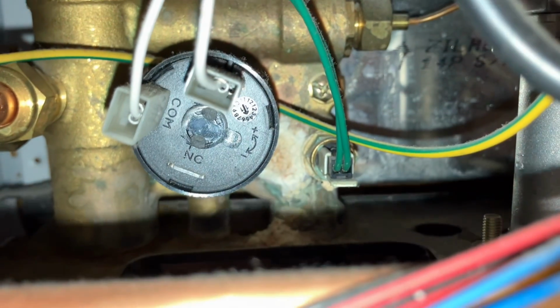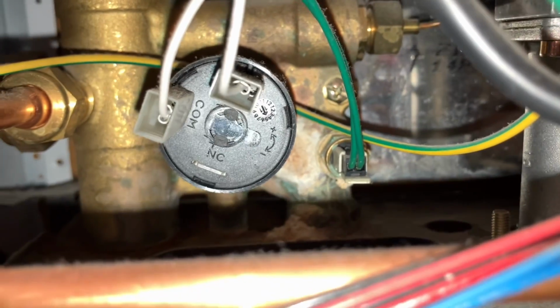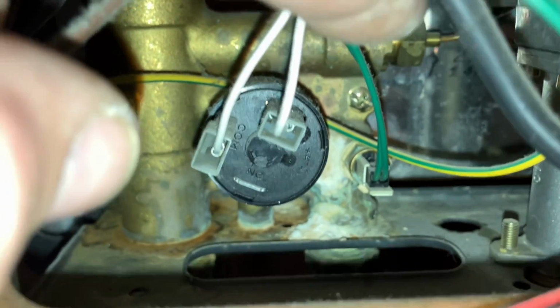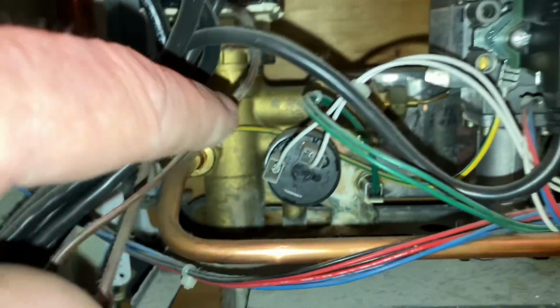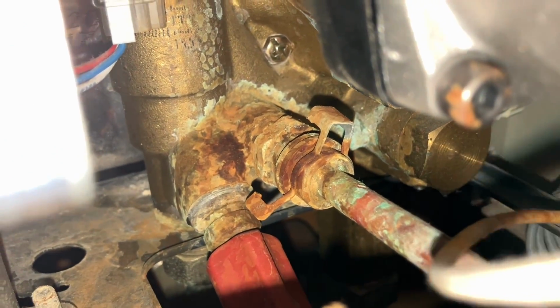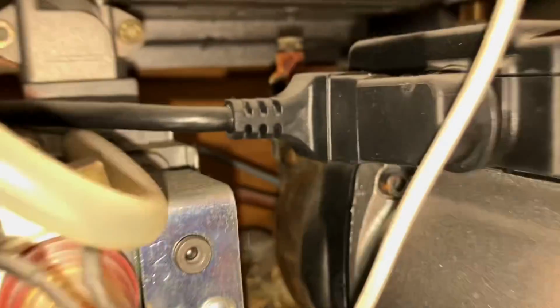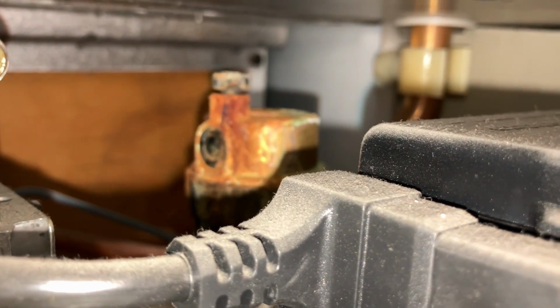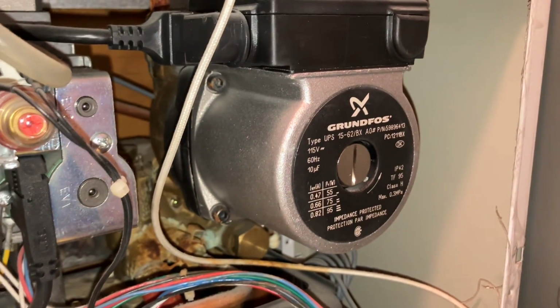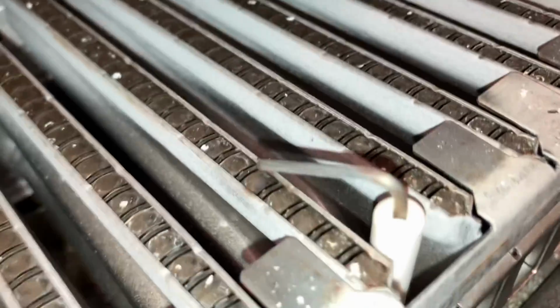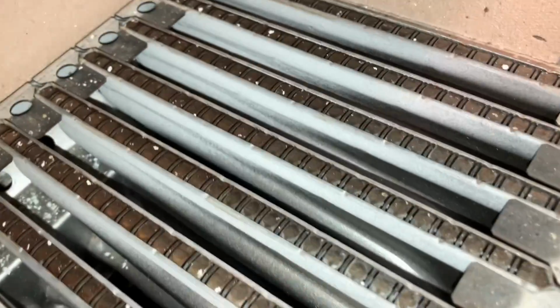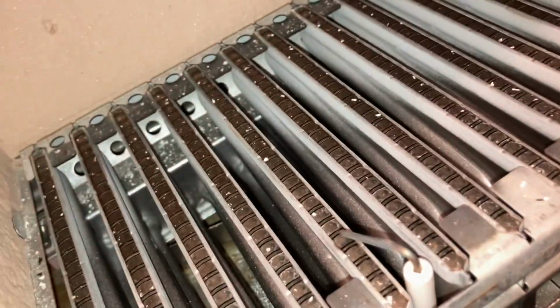Looks like some nice corrosion on the domestic hot water outlet side of the 3-way valve there. There as well. Oof, wow. Top of the automatic air valve on top of the internal Grundfos circulator. Our flame rods are pretty clean, but we'll take a little wire brush and clean them down.